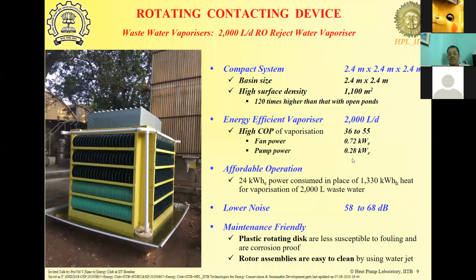So in this case, we have obtained COPs as high as 36 to 55. In fact, we have reached even 64 COP now. And although this is electrical COP, even if you convert it to thermal COP, it is still almost 10 times more, a COP of more than 10 to 20 compared to 3 to 4 for a thermal unit.